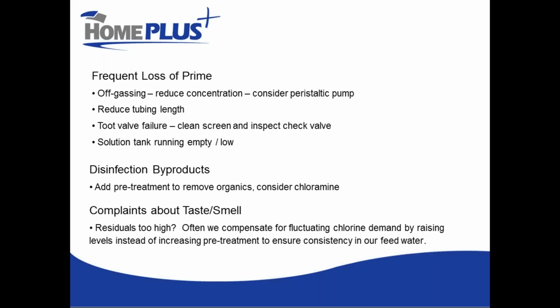Disinfection byproducts and complaints about foul tastes or smell. The more consistent we can be in our injection, and the more consistent we are in terms of our chlorine demand in our raw water, the less buffers we need to provide to ensure that we're always injecting enough. So when we have high chlorine demand, or especially fluctuations in chlorine demand that are pretty wide, what we often end up doing is setting our chlorine pump on the setting that we need to address the worst case scenario. The rest of the time, we're actually over-chlorinating above what we really need to. And that can create these undesirable tastes and smells.